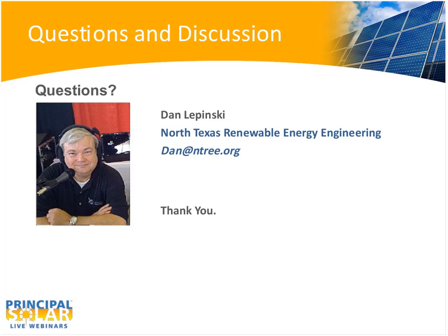Okay, great. Next question. You seem to be very positive about the idea of a 250-volt photovoltaic panel for film PV. Are there any new safety issues or other disadvantages that you would experience with 250-volt PV? Not really. Aside from the fact that, you know, I would not normally recommend that high a voltage for a string system. You'd have to parallel too many of the photovoltaic modules.